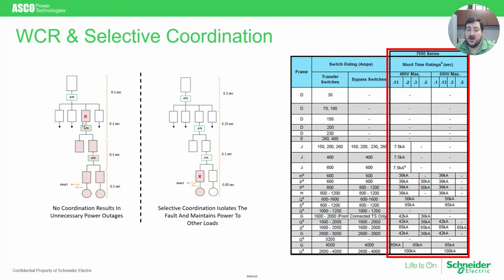And that takes loads offline, out of service unnecessarily. There is no reason, if there was a fault on this branch down here, for it to also take down this branch up here, for example. When you selectively coordinate your circuit breakers and your transfer switches, what happens is that the breakers closest to your loads must trip much faster than the breakers that are further up in your system. What that means, if there is a fault lower in the system, that breaker will trip before any breaker above it, minimizing the unnecessary power outage to other branches in the system.